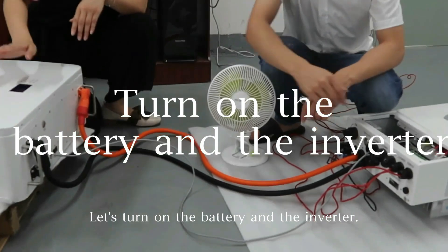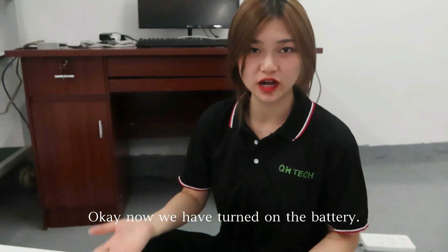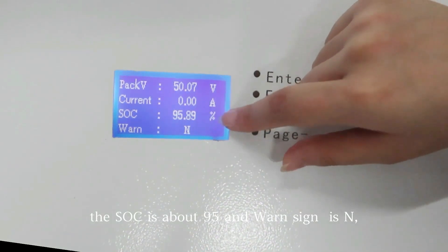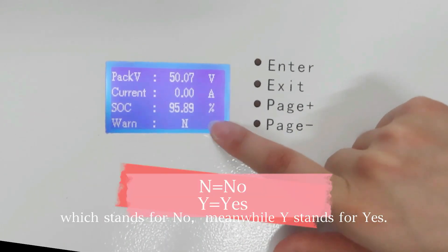Let's turn on the battery and the inverter. Now we have turned on the battery — let's see what the screen shows us. As you can see, the voltage is 50.07V, the current is 0, the SOC is about 95%, and the warn sign is N, which stands for no — meanwhile Y stands for yes.